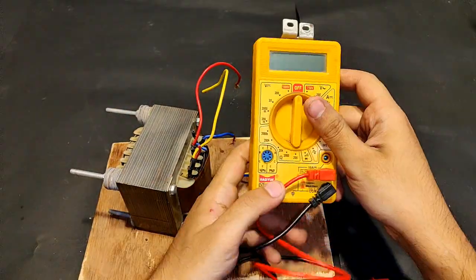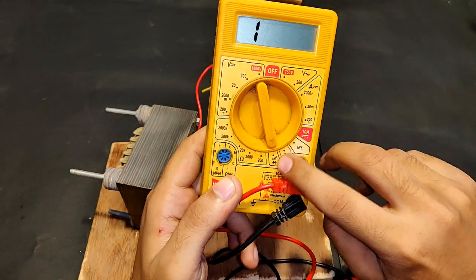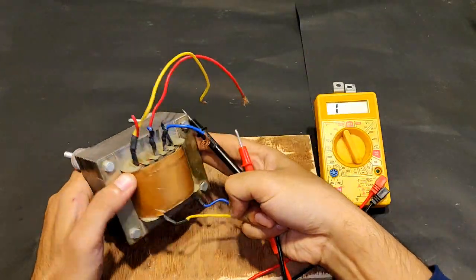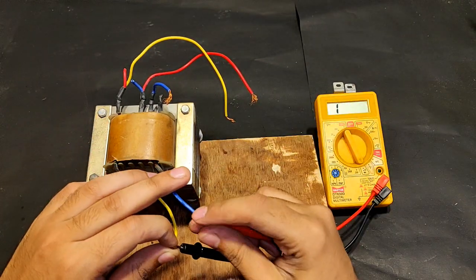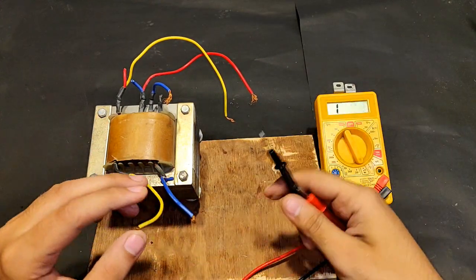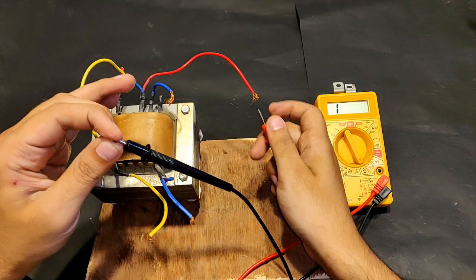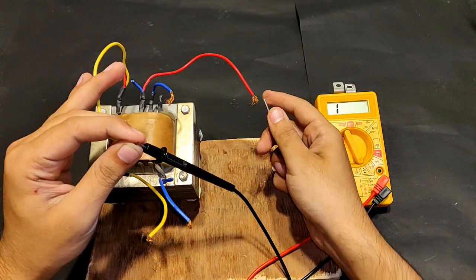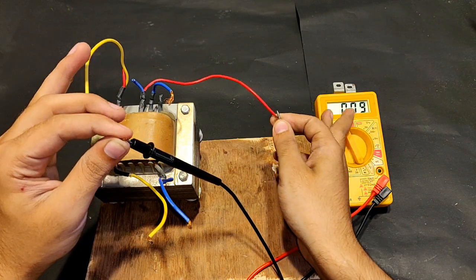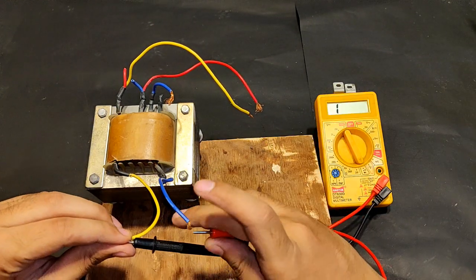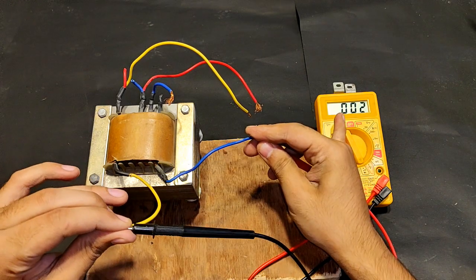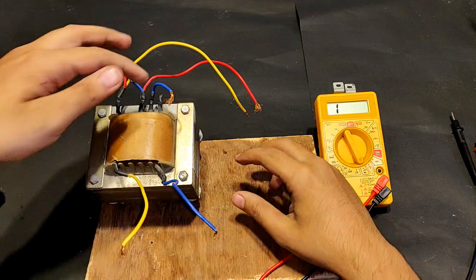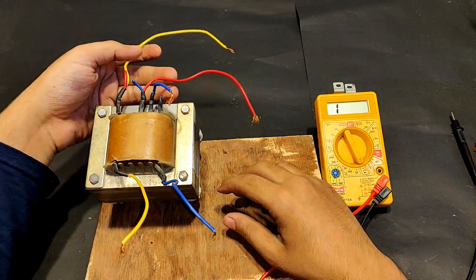The multimeter is pointed towards the continuity checking mode. First, the low voltage secondary winding high current side. Yeah, it's working. Now comes the high voltage side. The resistance is somewhere around 9 ohms on the high voltage side and only 2 ohms on the high current side. This confirms this is the high current side and this is the high voltage low current side.